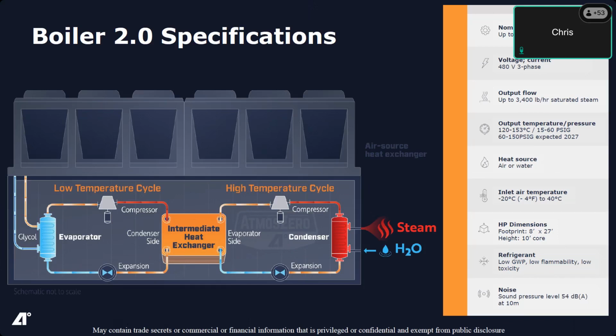If you run into more processing industries, sometimes you'll have higher psi requirements on the steam systems. We have a couple options there. We can either add an MVR and boost that pressure to the specified requested pressure, or we can look at tying that lower pressure steam around some pressure reduction valves in a facility. We've done both, and we're kind of advancing projects in both directions.